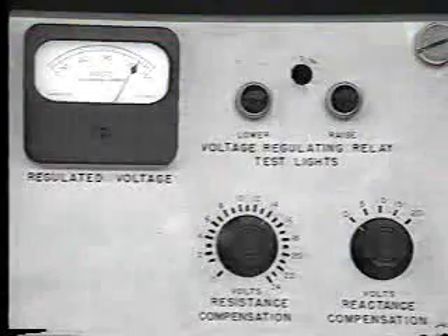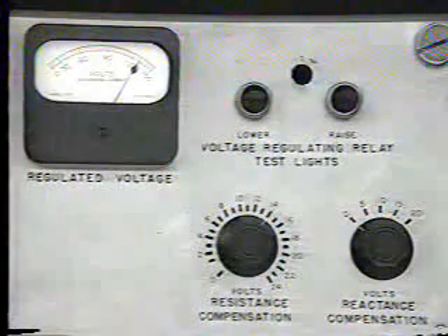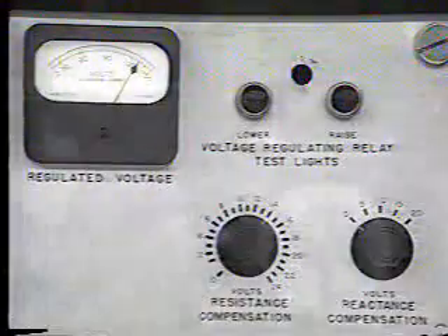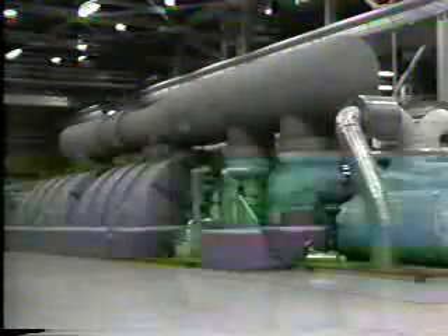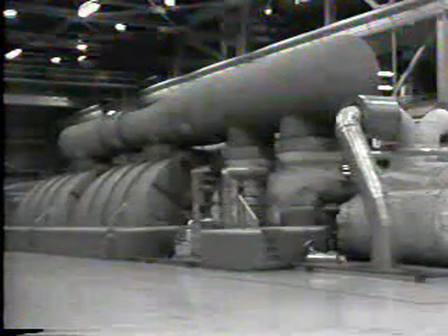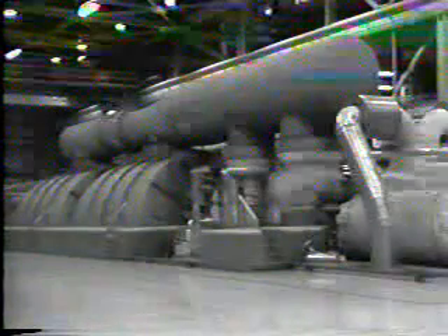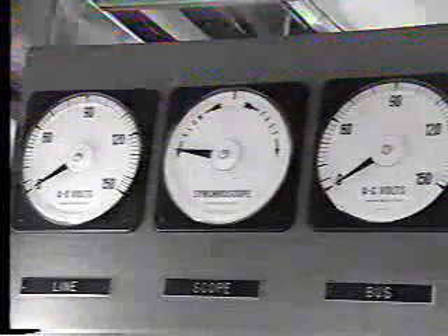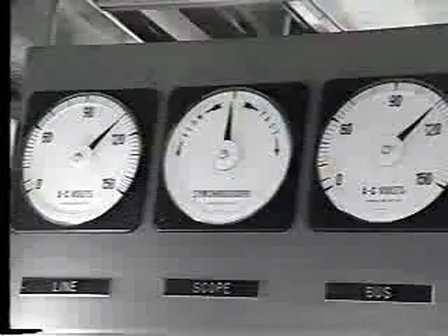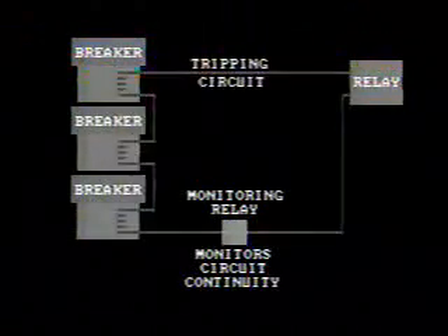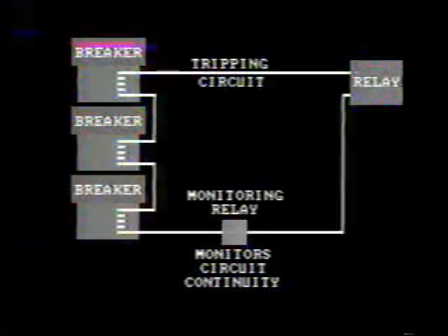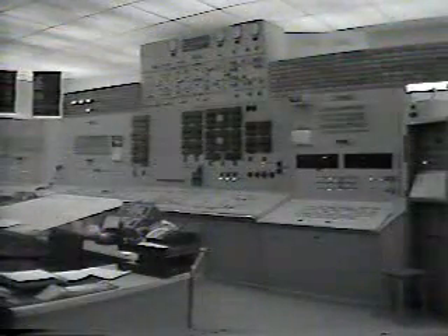However, there are other relays installed on the system which do not cause tripping of breakers for protection. But a knowledge of these relays is important in operating and maintaining the power system. One such classification is that of regulating relay. A typical example is the type of relay used to change the taps on a transformer. Another regulating relay is that used to adjust the governor set point on generating equipment and so control the power output. Synchronizing relays are used to check the phase angle before allowing the paralleling of two systems or an incoming generator. Another type of relay is the monitoring relay. An example of this is where the relay is used to monitor the continuity of circuits within breaker trip circuits. Any failure will result in an alarm to the operator.